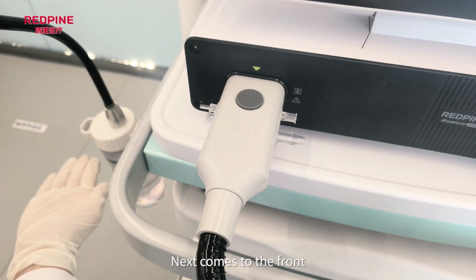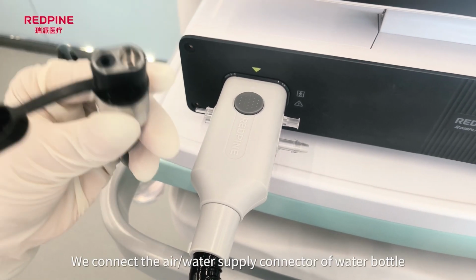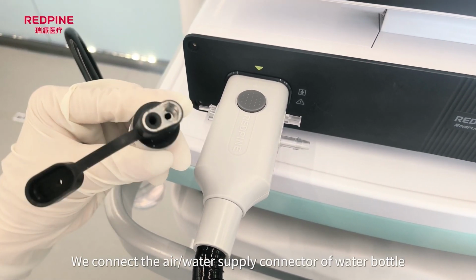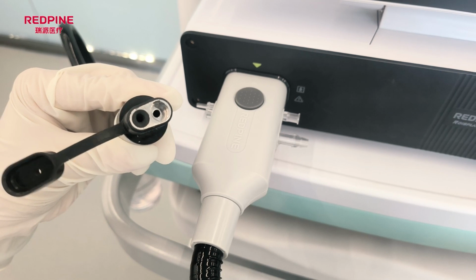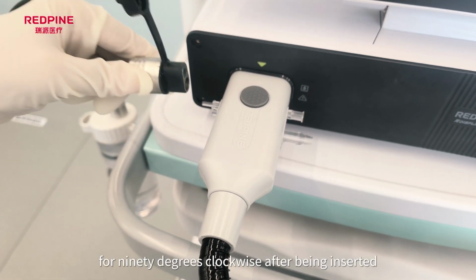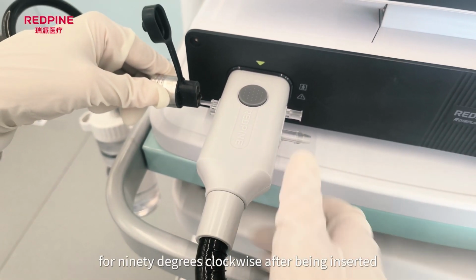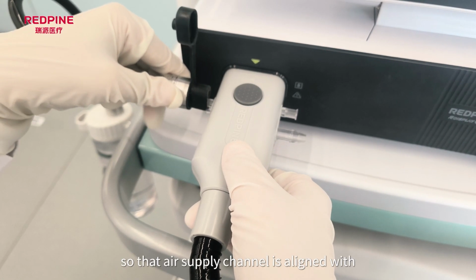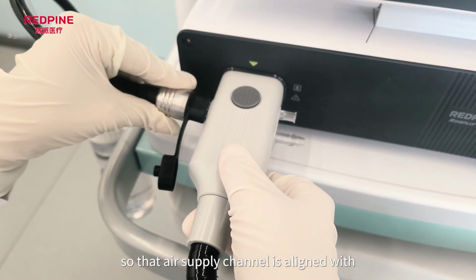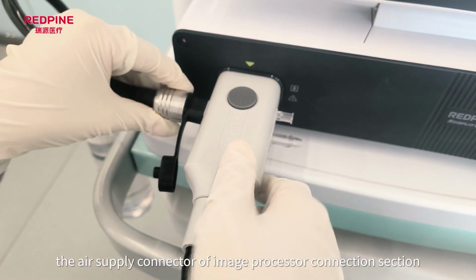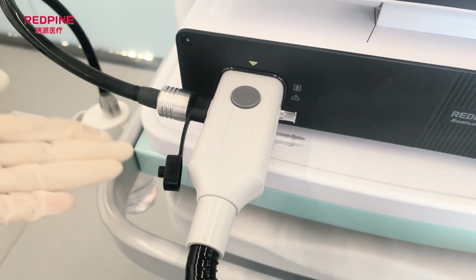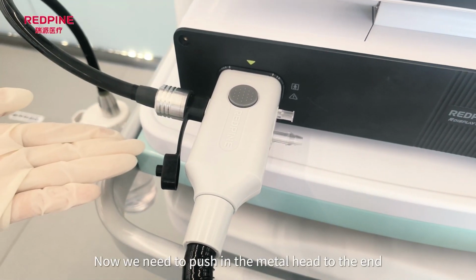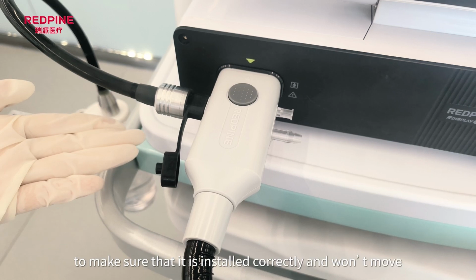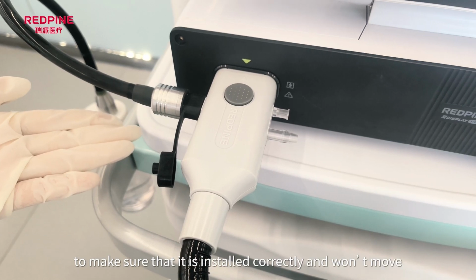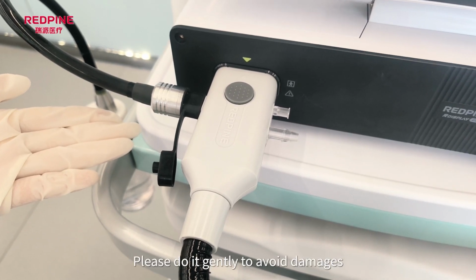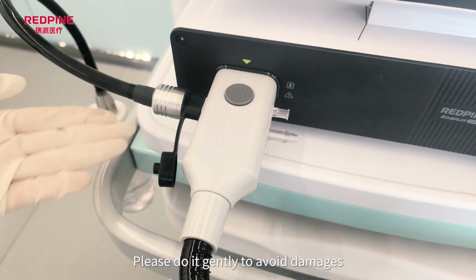Next comes to the front. We connect the air and water supply connector of water bottle. The metal head should be rotated for 90 degrees clockwise after being inserted, so that air supply channel is aligned with the air supply connector of image processor connection section. Now we need to push in the metal head to the end to make sure that it is installed correctly and won't move. Please do it gently to avoid damages.